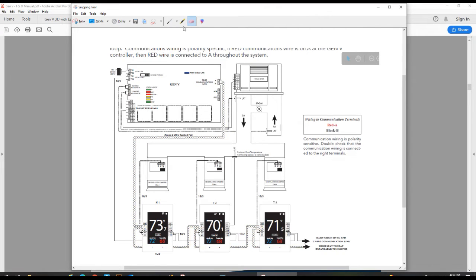Alright, wiring into our dampers. Each thermostat has an RC, RO, and MC terminal. So using 18 gauge thermostat wire, 18/3, you're going to go ahead and wire up to the respective damper that it is controlling. And you'll wire it up and match it at the terminals, MC, RO, and RC.